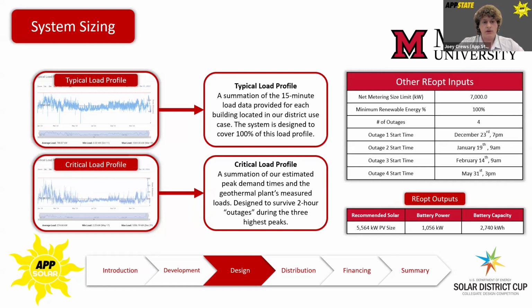This resulted in a critical load calculation consisting of a combination of the university's estimated peak demand values and the entire load of the geothermal energy plant. We also ensured that the system would survive the 4 highest peaks of the geothermal energy plant's load and peak demand simultaneously, allowing for additional loads to be served by the batteries in case of an outage. During an outage, the geothermal battery will typically be able to serve additional loads, as it is going to have ample capacity. In fact, the dedicated geothermal plant battery is large enough to power the average load of the geothermal plant for almost 6 hours.